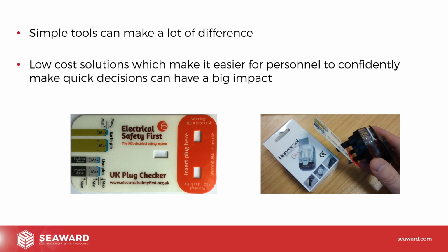So you can simply use this, as you can see on the right hand side there, to plug it in, and you can see, are the pins correctly spaced? Are they the right size? Can I see any of the red area, the area that I shouldn't be able to see? And also on the left hand side, you'll notice that there are diagrams on there, and you can use those as a bit of a gauge, put those up against the size of your earth pin and your live pins, and actually see whether it meets the correct size for the insulation and the size of the metal areas on the pin as well.